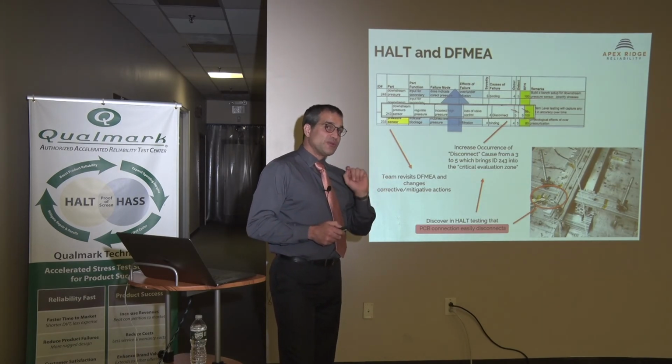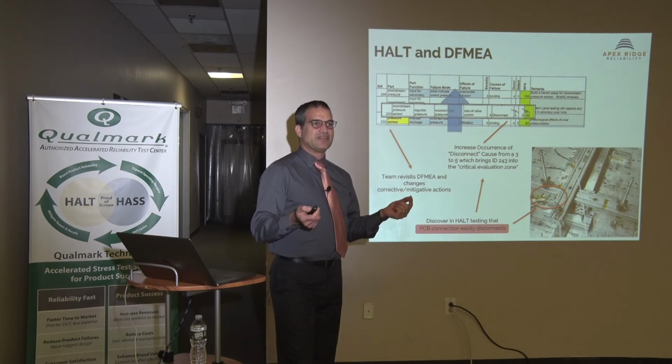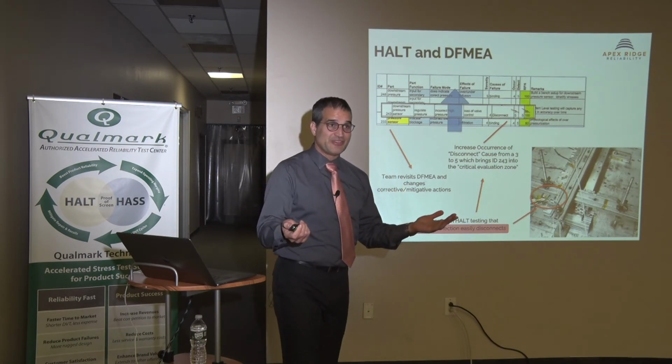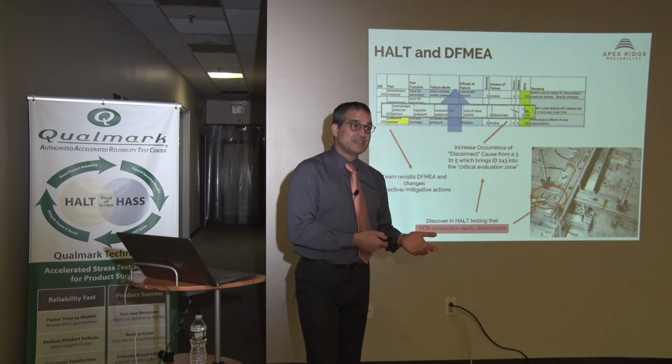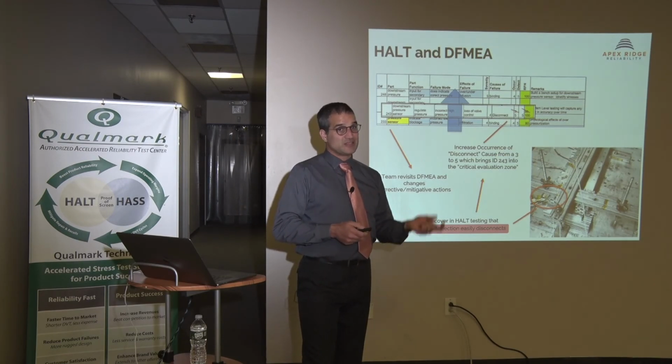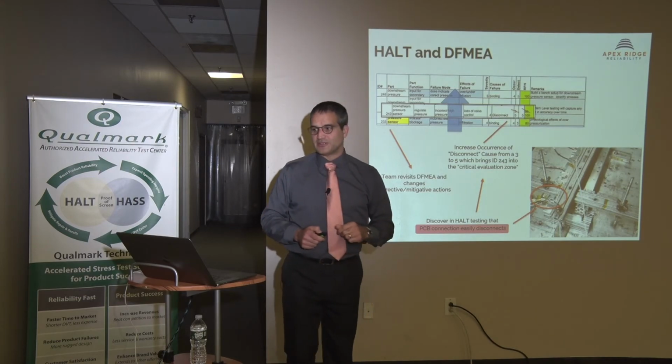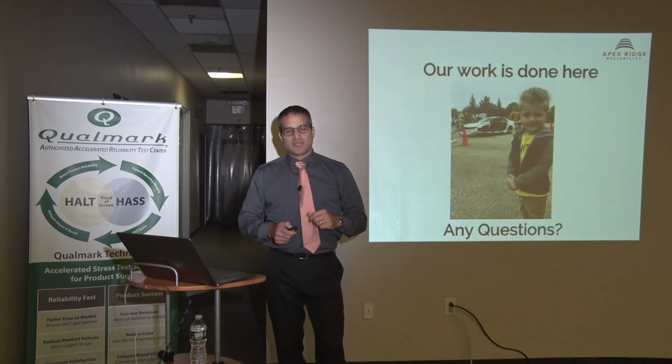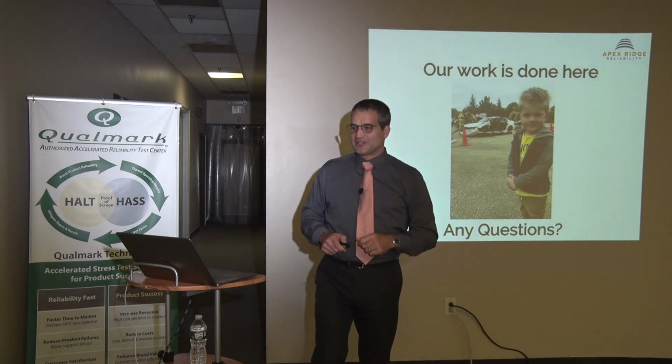So we realized that, of course, if you're sitting down as a team and hypothetically looking at failures, and then they get actual data, we realized, wow, this actually was much more serious and should be addressed. And we found that in HALT testing as opposed to finding it from field data and field feedback, which is much more difficult. So I think our work is done here talking about the HALT testing.